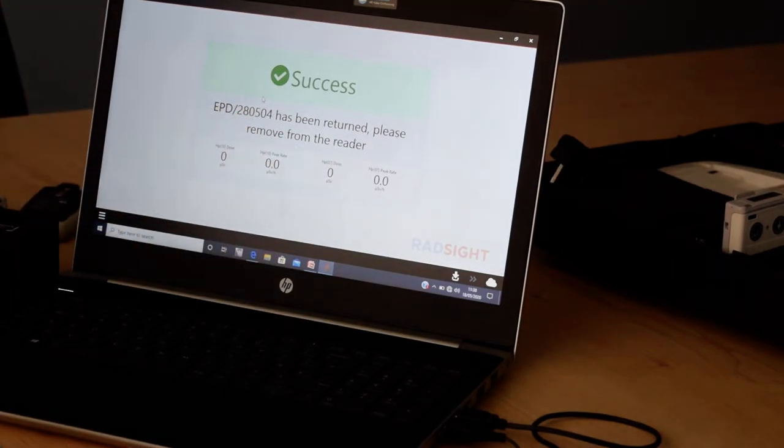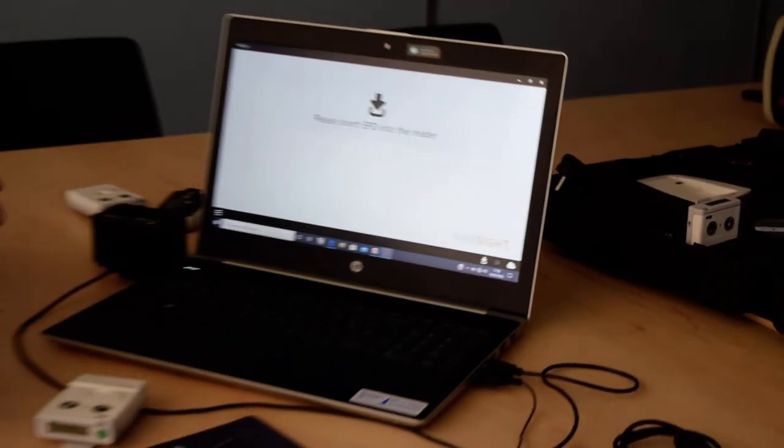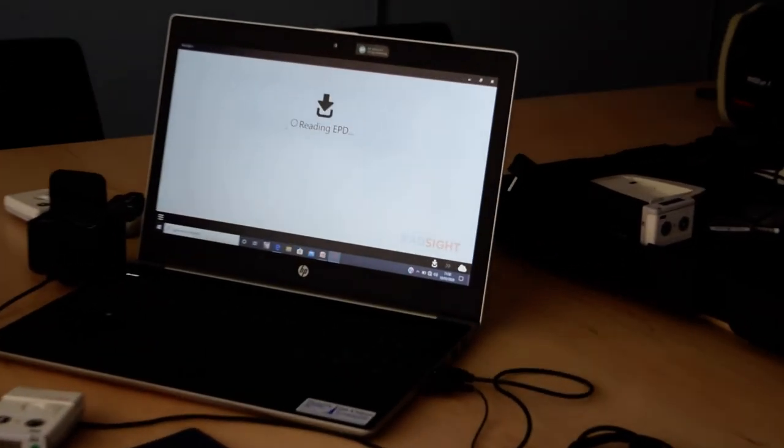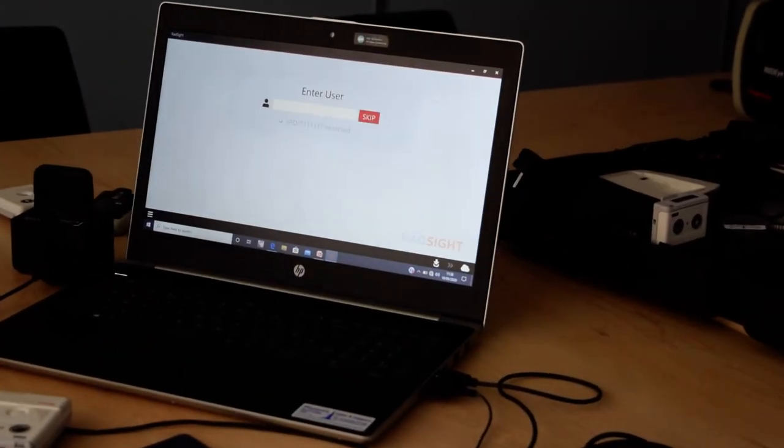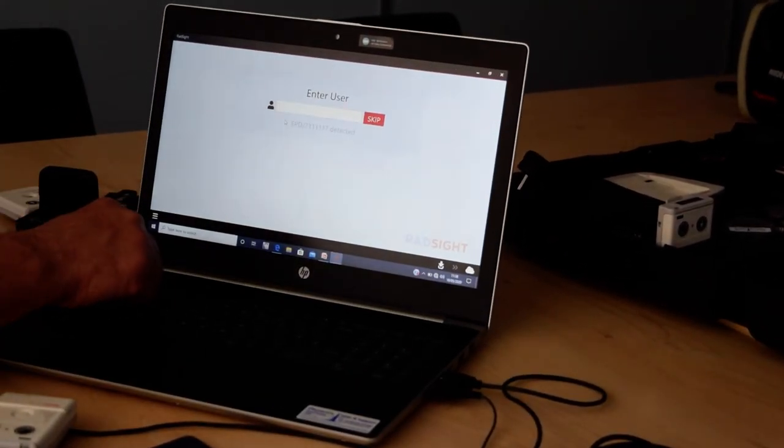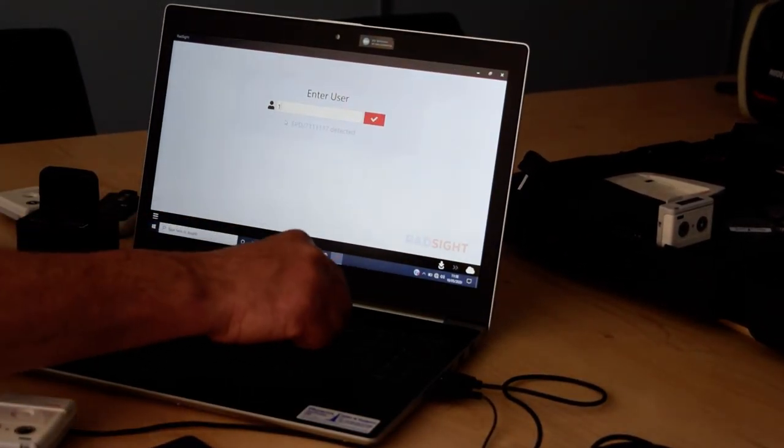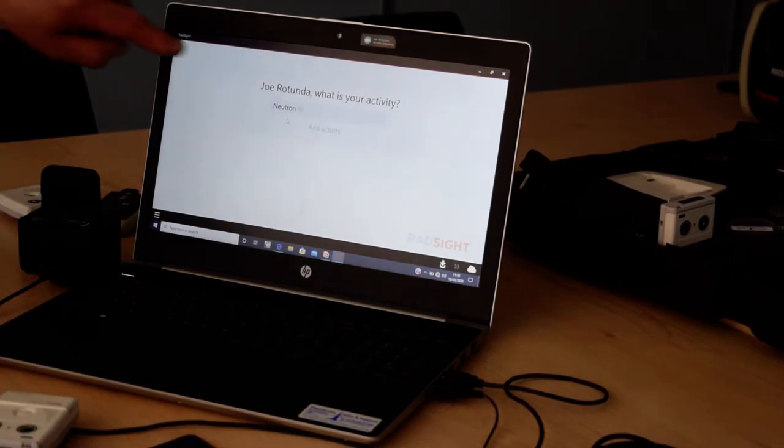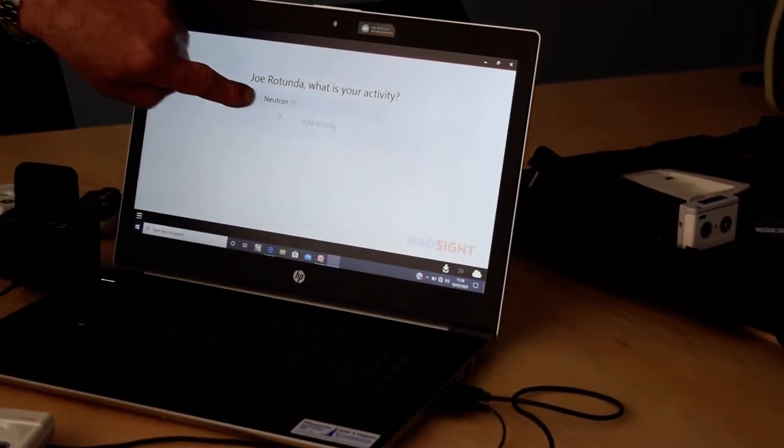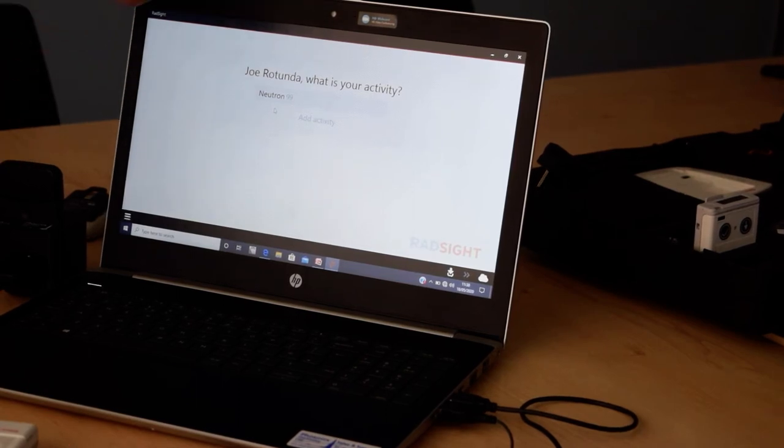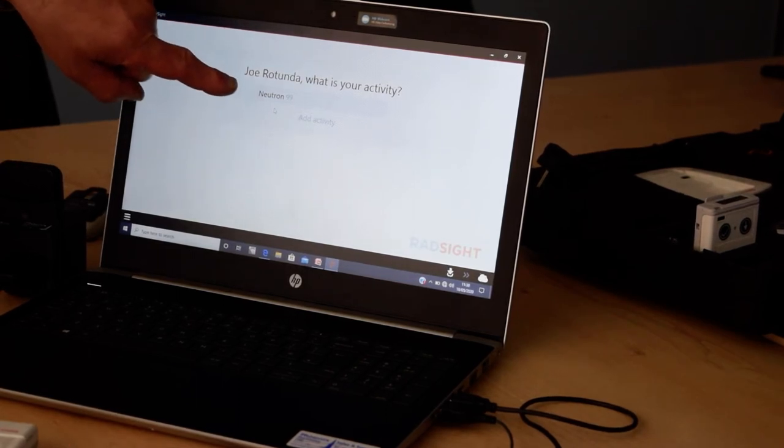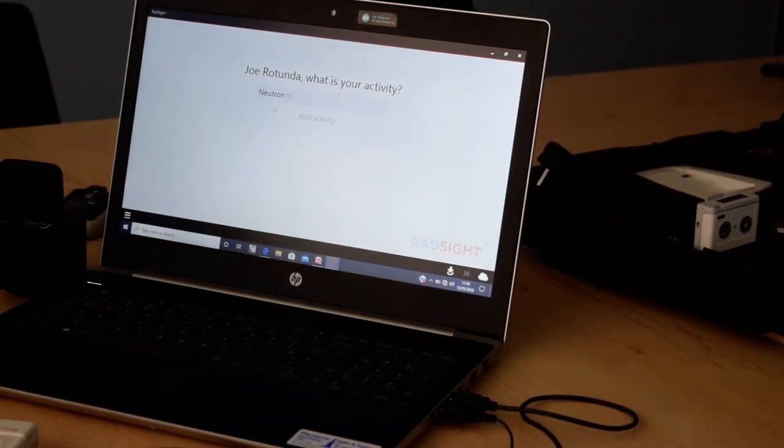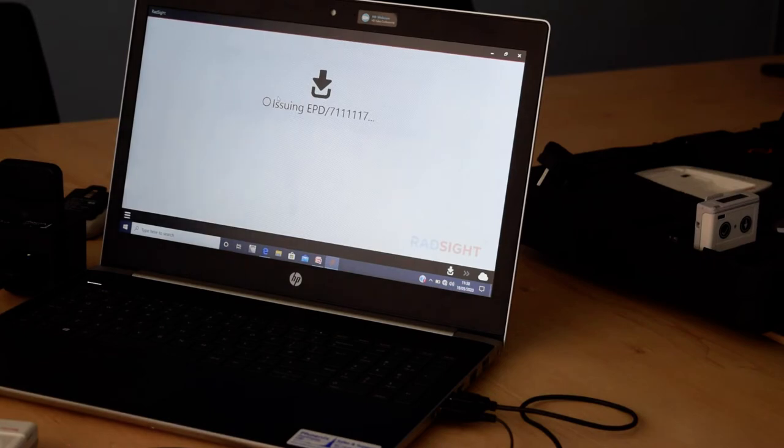If I want to issue a neutron dosimeter, again, I just pop in the dosimeter into the docking station, I can now put in someone's ID number. It's now recognized on the software that this is a neutron dosimeter, it will only issue it to an active neutron site, so this is going to the neutron site.